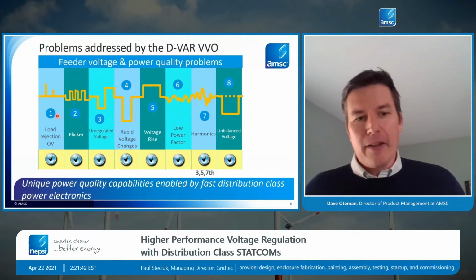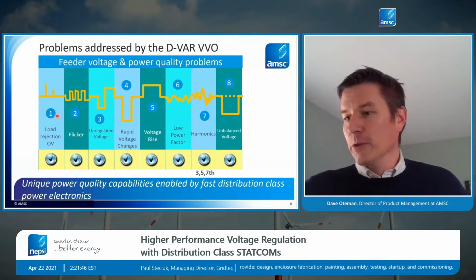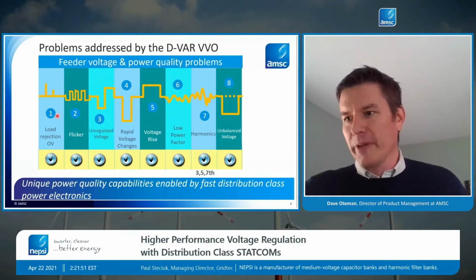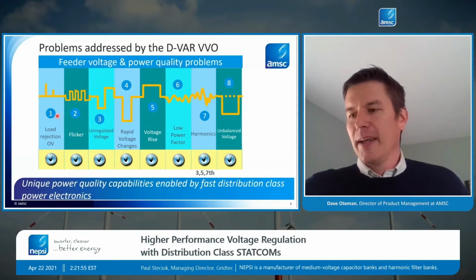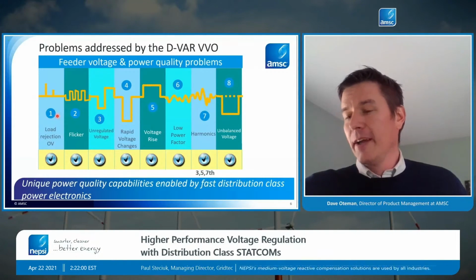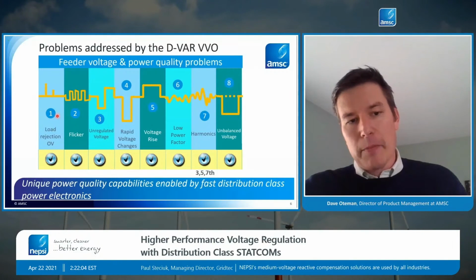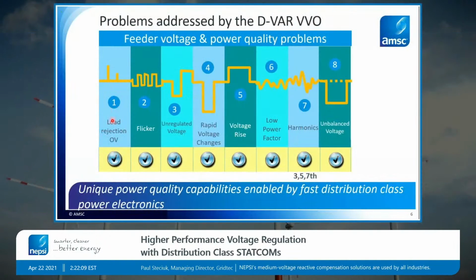So load rejection over voltage. That is a common problem on longer feeders where you lose a load suddenly, and that can happen for a lot of reasons. A recloser opens, or a large customer has an issue and trips their breaker. It's a very common issue towards the end of a feeder where the voltage can spike up to 20%, 25%. A STATCOM on the end of a feeder can pull that voltage right down and actually prevent it from happening in the first place. Flicker has a lot of causes, anything in the realm of crushing operations. We see electric industrial heating very commonly causing flicker. Arc welding and arc furnaces cause flicker on the distribution system. A STATCOM is in fact fast enough to compensate for flicker and bring those feeders into compliance, not just for the industrial customer, but for all the other customers.